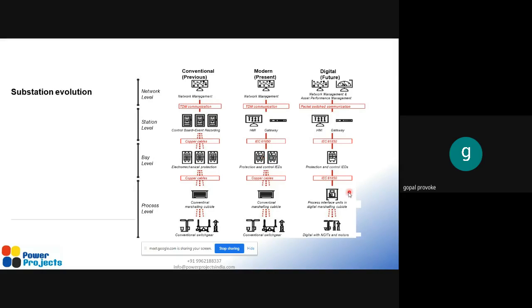This will be sent as a voltage or current signal. In a digital substation, it will be sent as data instead. So there is a major difference between signal and data. A signal contains some minimum voltage, like 4 to 20 milliamps, or a 1 volt or 5 volt system - sent as electrical signals. But here it is sent as data, similar to internet email or a WhatsApp message - we receive it as data.